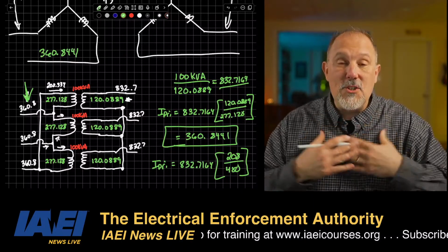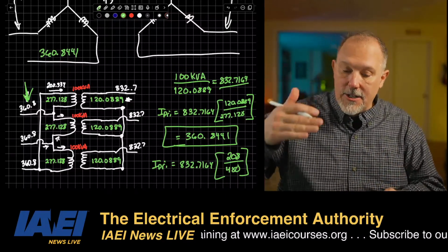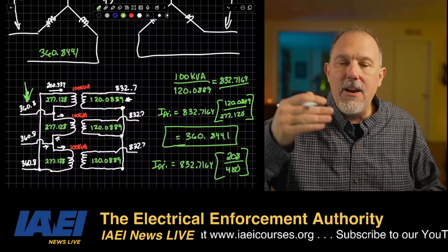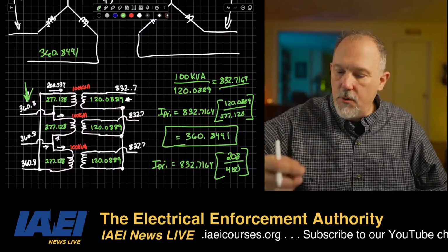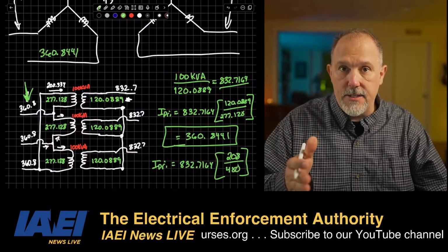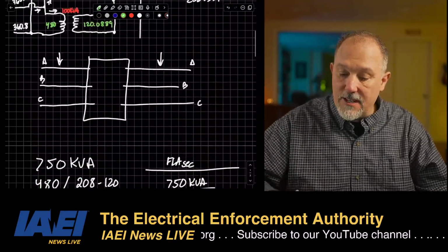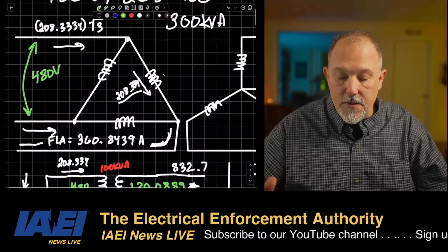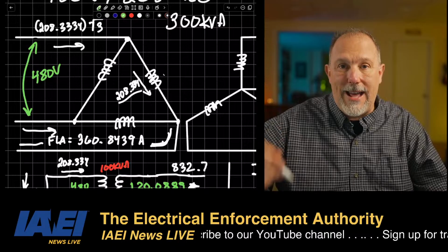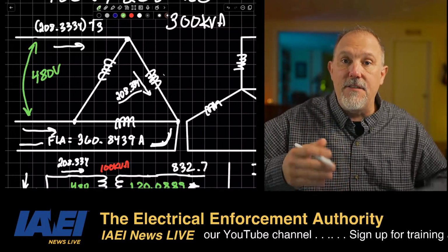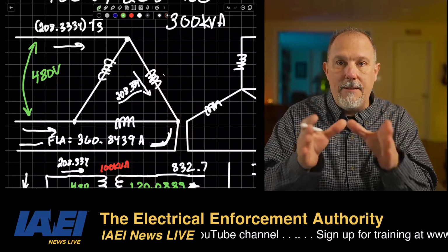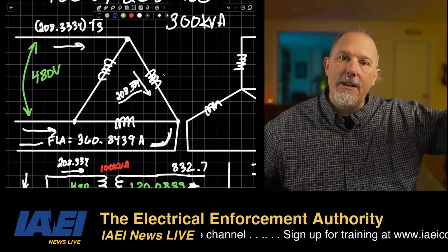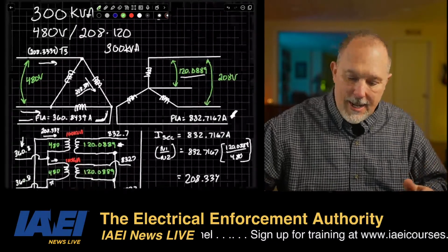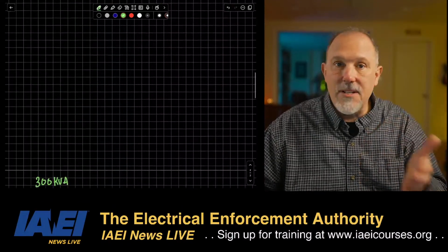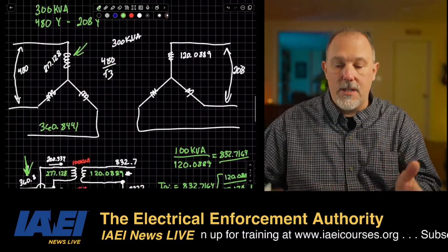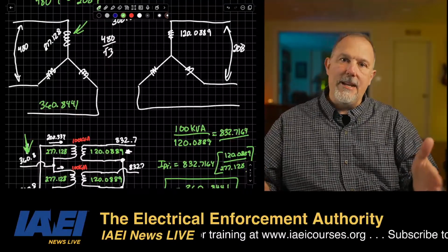But what I wanted to do today was say, look, they are equivalent. Both methods. If you want to do the single phase, you can. You've got to think about the configuration on the primary. Is it a delta on the primary? And what is the current you're actually calculating on the line side of a single phase transformer when you take that method, if you're not going to use line to line on the secondary, line to line on the primary? And it doesn't matter if it's delta to Y, if you're using line to line voltage on the primary, line to line voltage on the secondary.